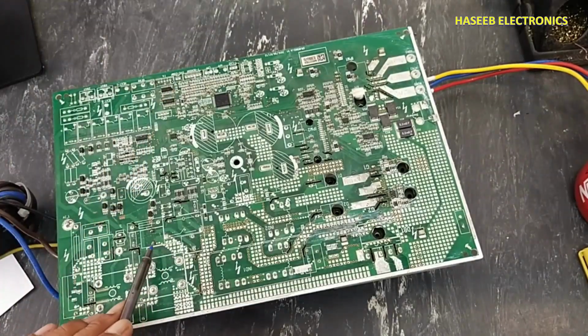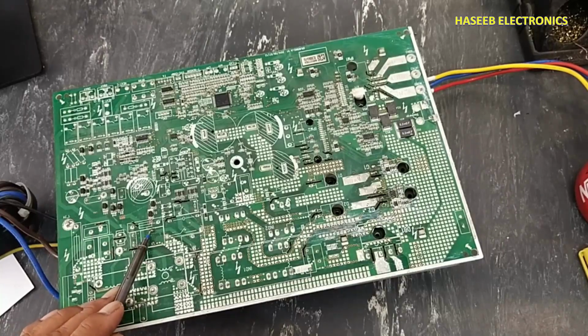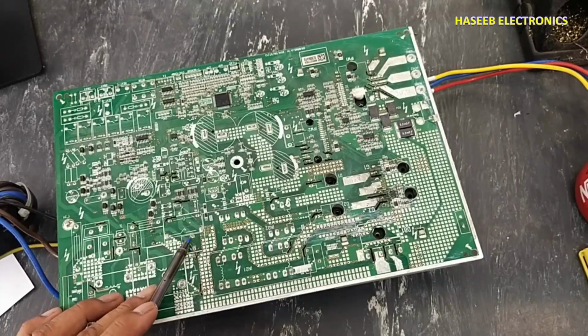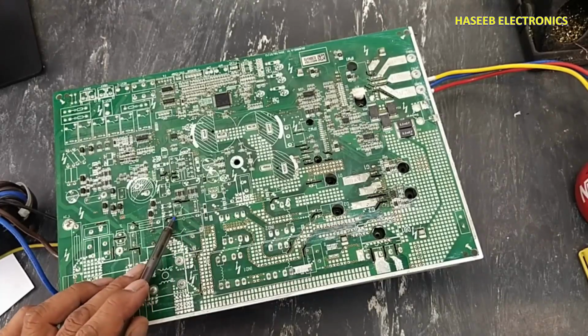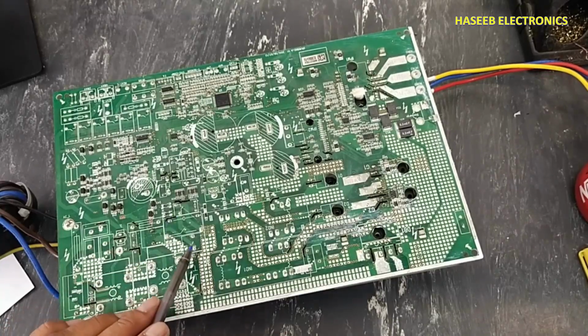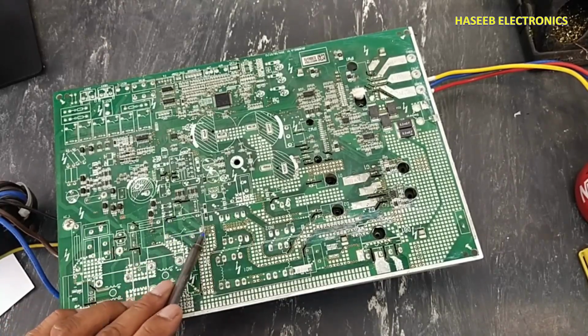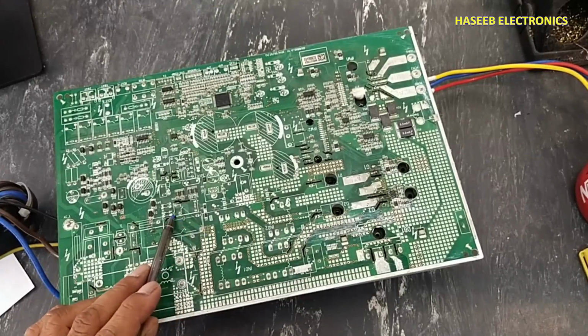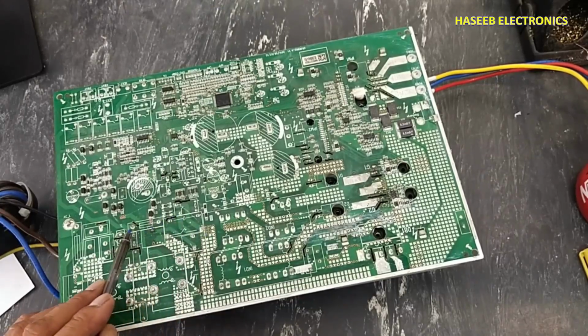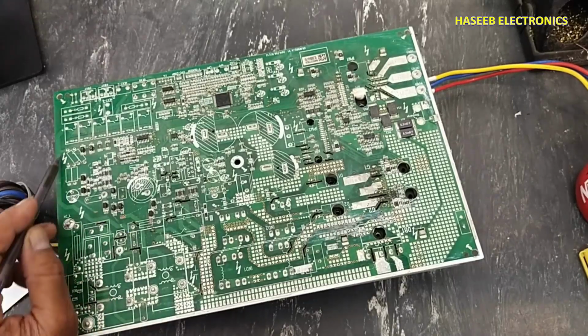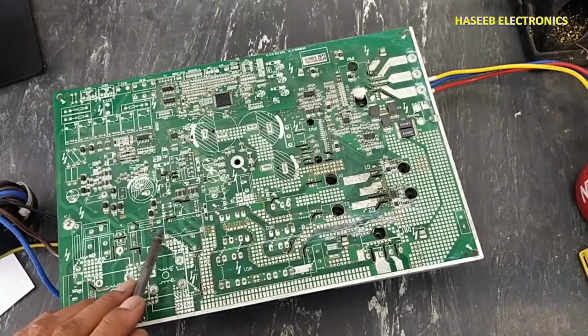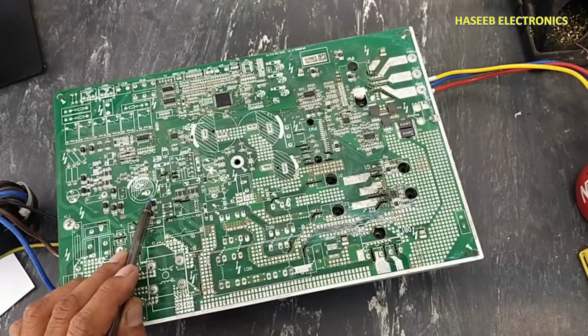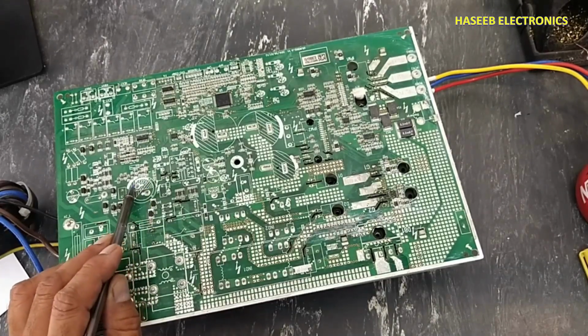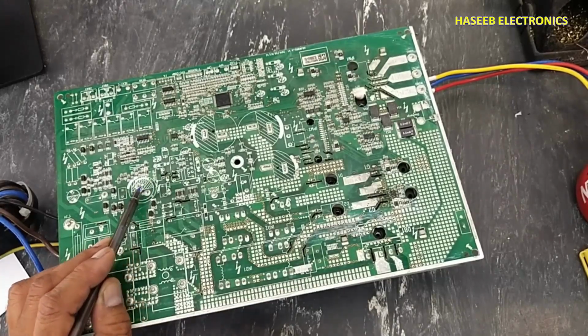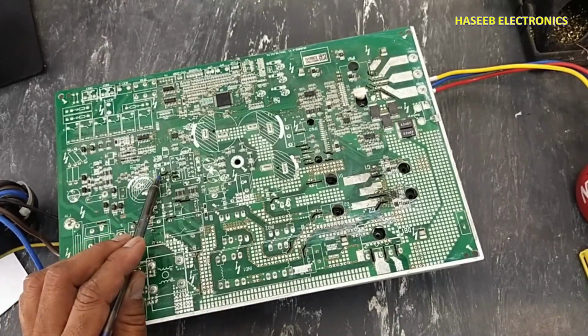Line voltage here will reach this first PTC. This is a 50 ohm PTC from here to here, then from here to here. It is reaching here at this point. And here we have the relay, the bypass relay. From here, this voltage will reach this point. This will provide it to the common points, and at the same time voltage is reaching this rectifier set, and this voltage will reach this capacitor, that is the capacitor for this low voltage power supply.